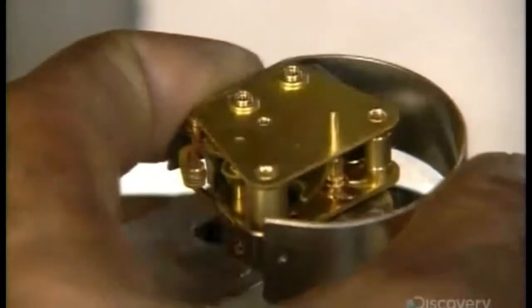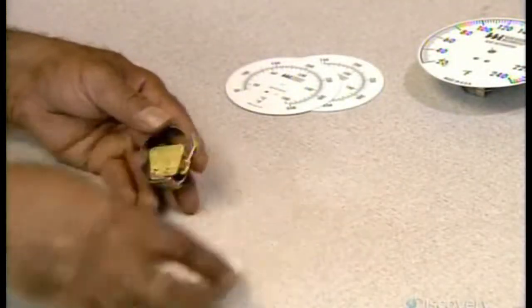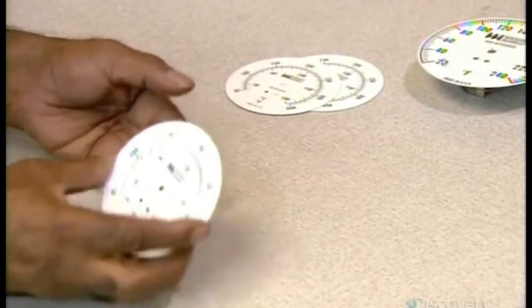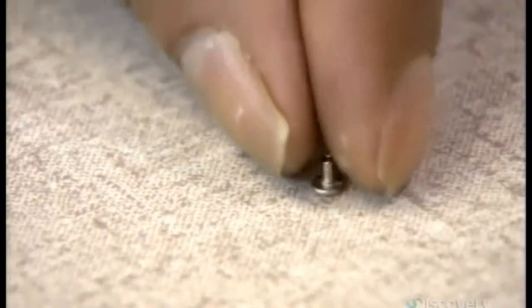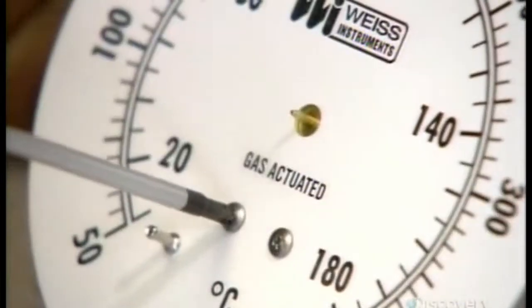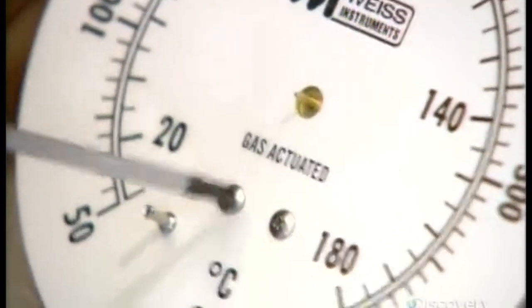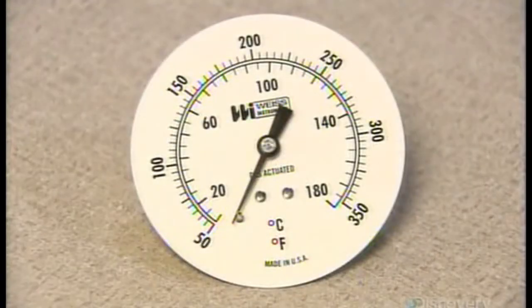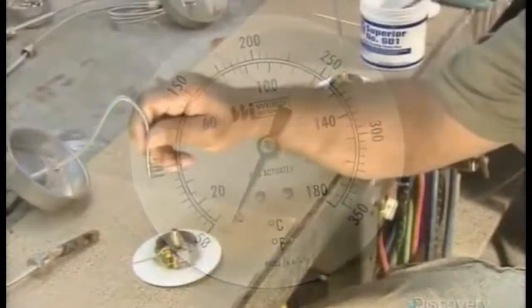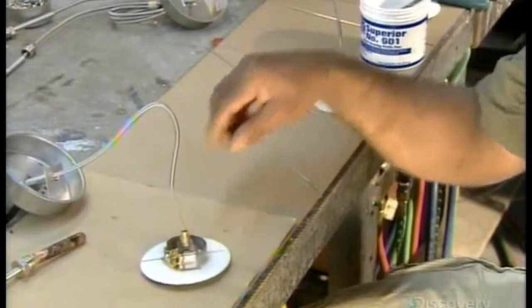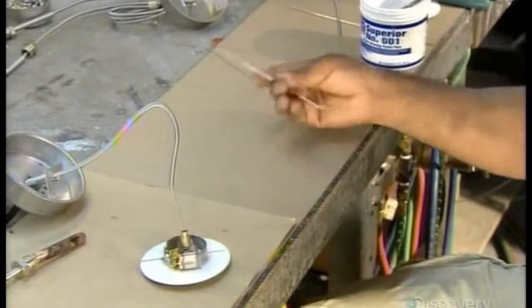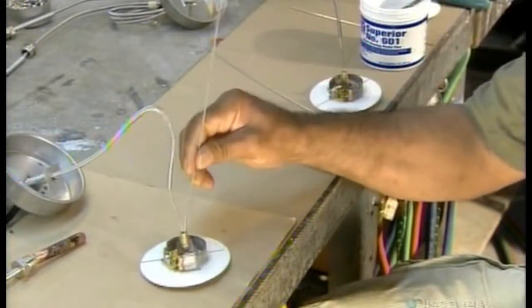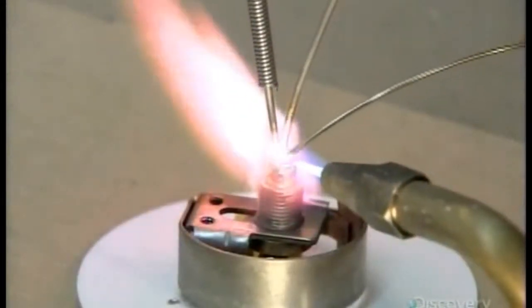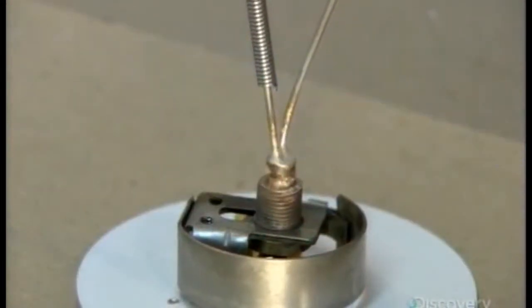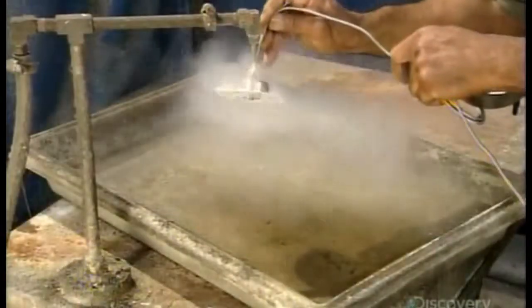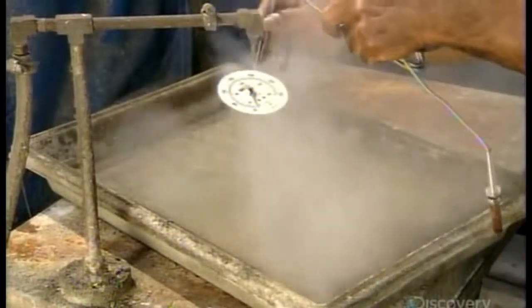that will translate the linear movement of the Bourdon tube into the rotational movement of the thermometer pointer. He screws the dual temperature dial to the Bourdon tube assembly. The more detailed and extensive the scale, the bigger the dial. This one is mid-sized. And now everything comes together as he tethers the sensing bulb along with a short fill tube to the back of the Bourdon tube assembly. Using a brazing torch and solder, he seals the connection. He then steam cleans the brazed joint.